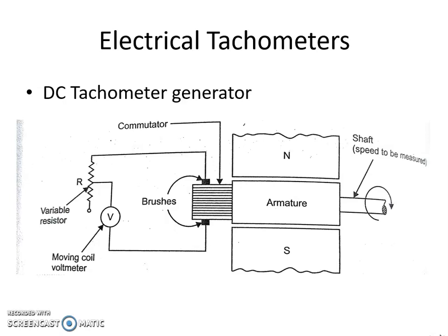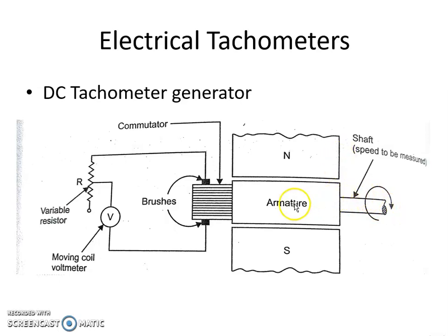This is the diagram of the DC tachometer. It consists of a shaft whose speed is to be measured. The shaft is connected to an armature, and there are brushes on the armature. The armature is kept between the two poles of a permanent magnet, providing constant flux or constant field excitation. When the shaft rotates, the armature also rotates, and EMF will be induced across the brushes. This is connected to a moving coil voltmeter through a variable resistor.